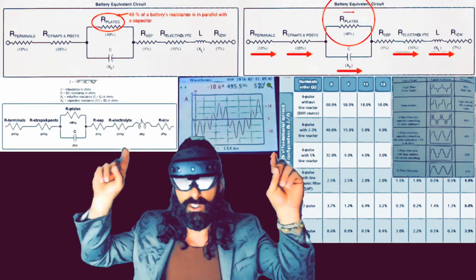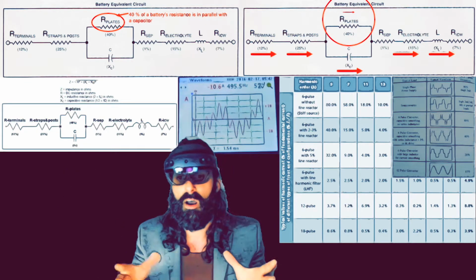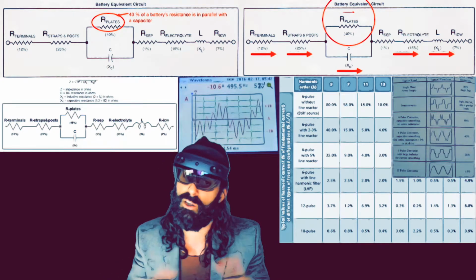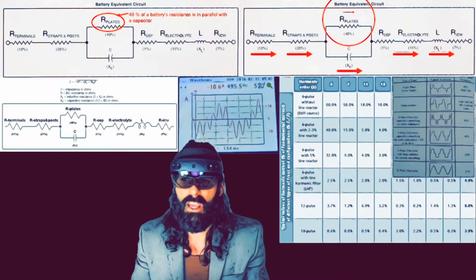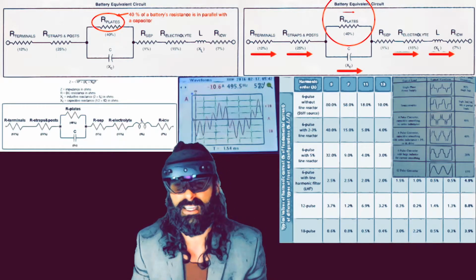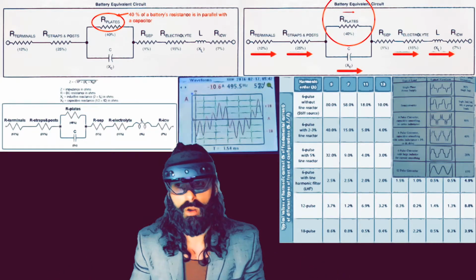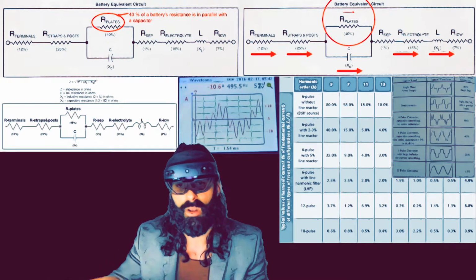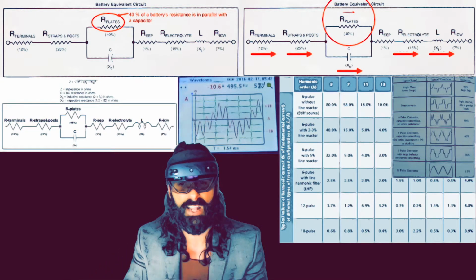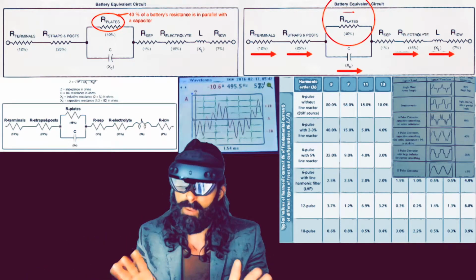So you can see these two basic fundamental principles: based on the frequency of the testing device and the amp hour of the battery, that determines the resolution if you're using an AC-based signal. But I always ask everybody, if you're using a battery that supplies DC current, why are you testing it with an AC signal source? It makes absolutely no sense at all. The DC current is going to feed the inverter, and that's going to be supplied to the load. The battery is not supplying an AC current to the inverter at all. So it doesn't make a whole lot of sense to me.